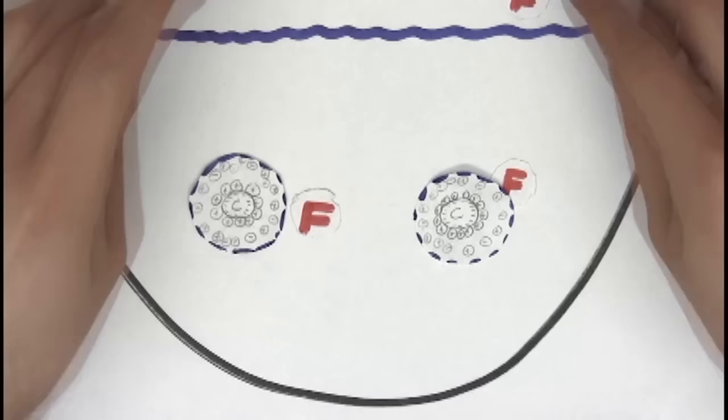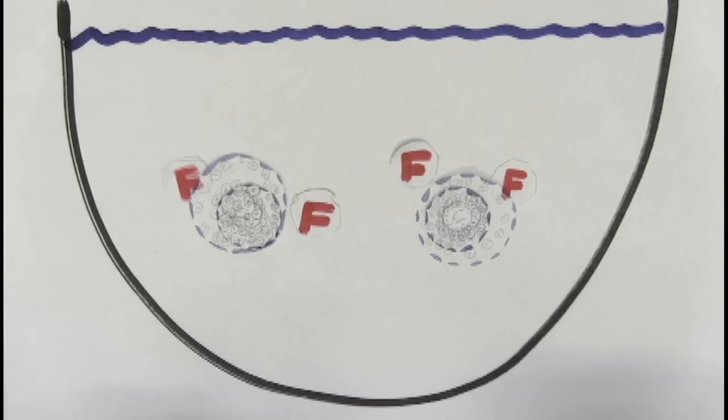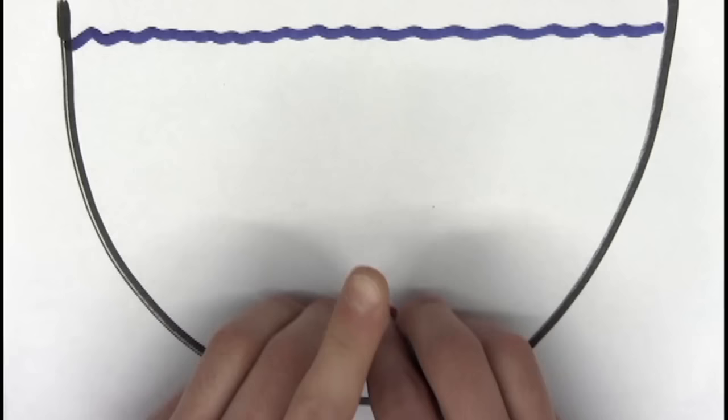Once the flocculant is added, it adheres to the surfaces of the particles, compressing the double layer and allowing the colloids to stick to each other and form flocs. These flocs are now heavy enough to settle to the bottom by gravity.